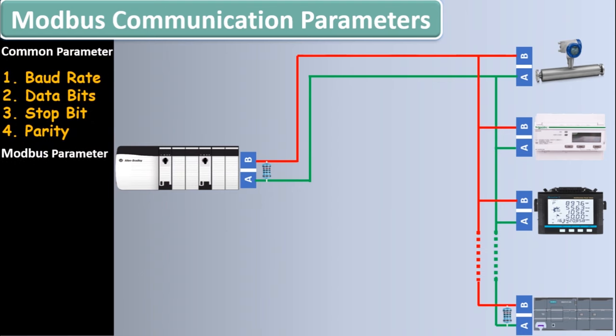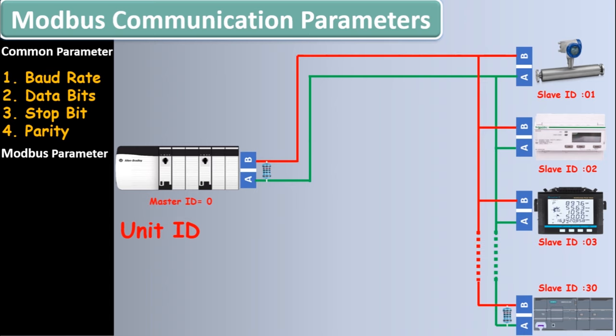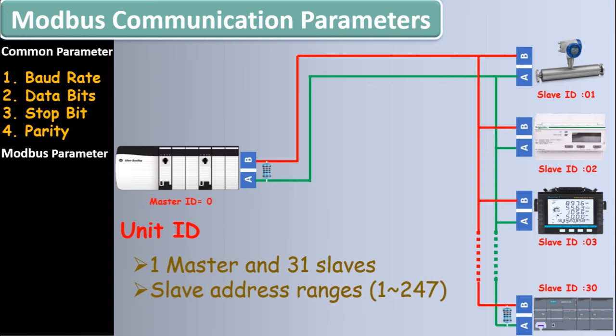Now we will see the Modbus parameters one by one. The first Modbus parameter is the unit ID. Every device in a communication network has its own unique ID. In this animation, the master has been given ID 0, and slaves have been given IDs 1, 2, 3, and 30 respectively. In a Modbus RS485 communication loop there is 1 master and up to 31 slaves, but the number of slaves can be increased using a Modbus repeater up to 247. So the slave address ranges from 1 to 247. Modbus communication is always initiated by the master; the slave never transmits data without receiving a request from the master, and slaves never communicate with each other.